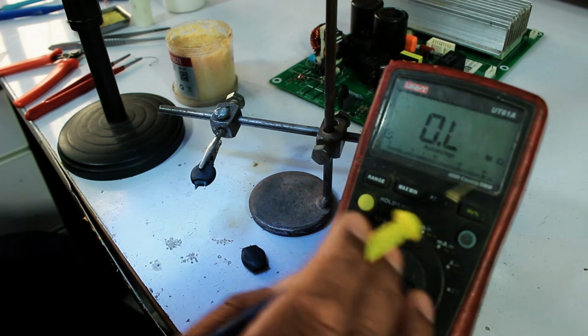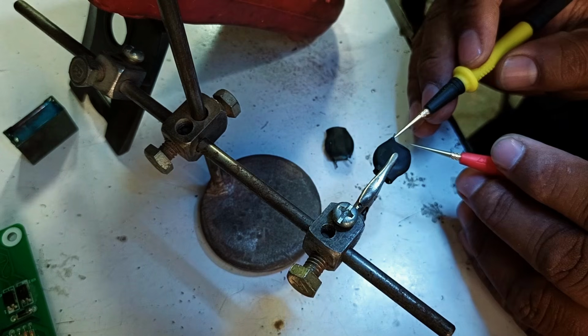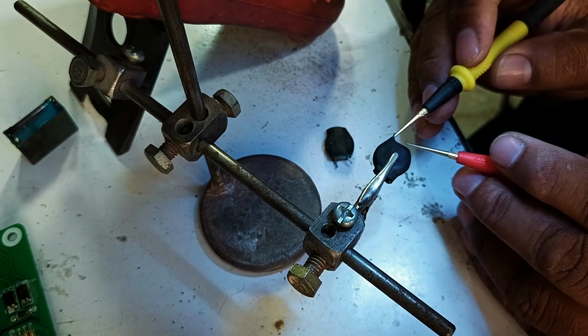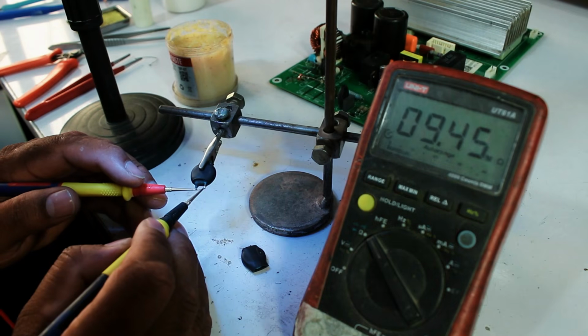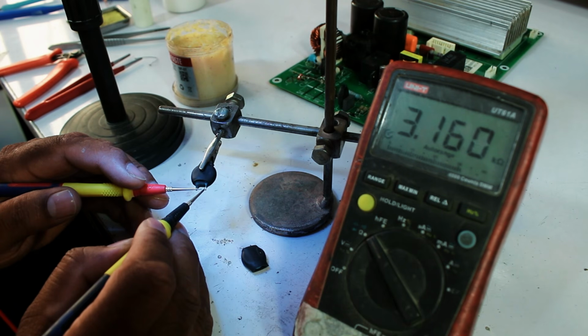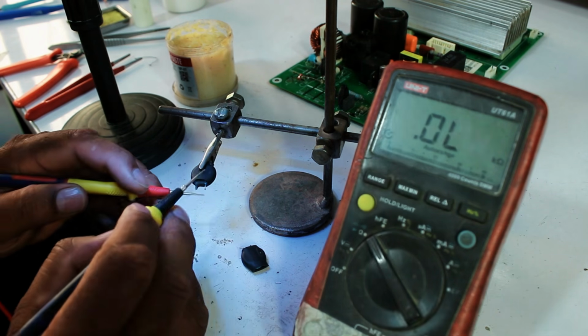We will check it in resistance mode. Look, when I connect one probe here and the other probe to the second leg, it is showing direct resistance. It is showing 3.168 kiloohms, which means this ZNR has become short-circuited.